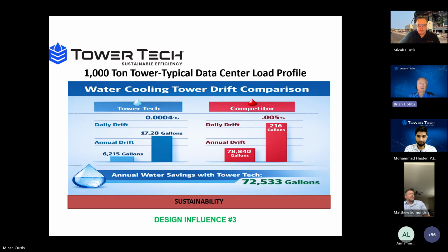As we spoke about earlier, the drift coming out of a conventional competitor's cooling tower is about 216 gallons a day. That's 78,000 gallons a year of water going up into the atmosphere. With a TowerTech cooling tower, because of our lower drift emission rates, we're at 17 gallons a day of drift coming out of the same size cooling tower. That's 72,000 gallons a year that we're actually saving the customer, but we're also not putting that vapor or the water droplets out into the atmosphere, therefore reducing the risk of Legionella into the atmosphere.